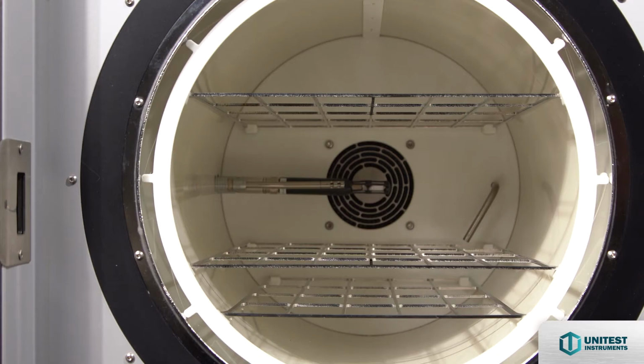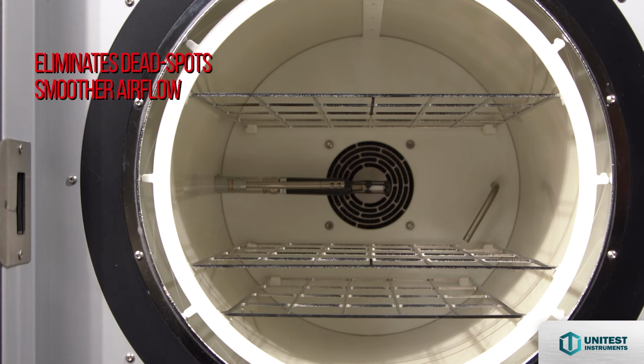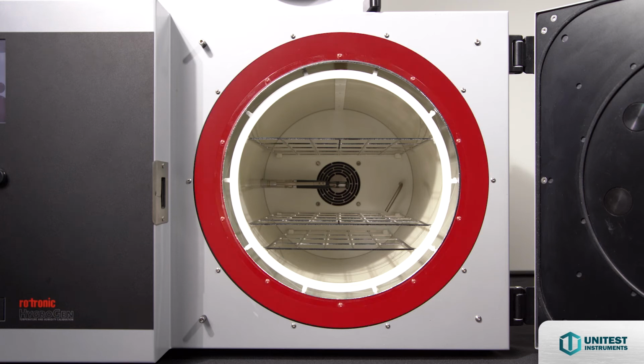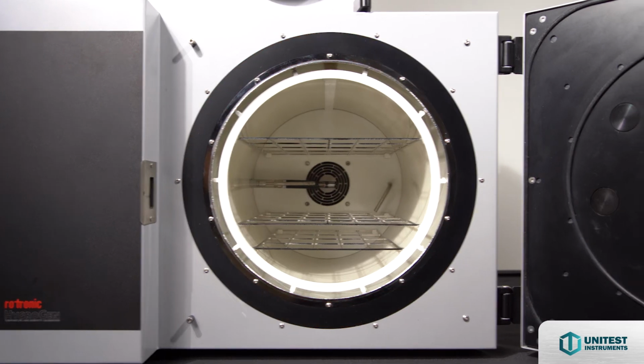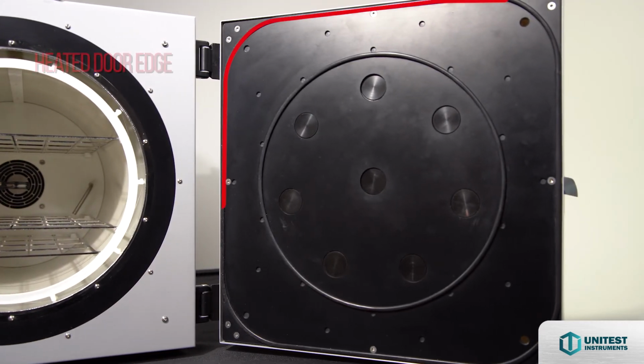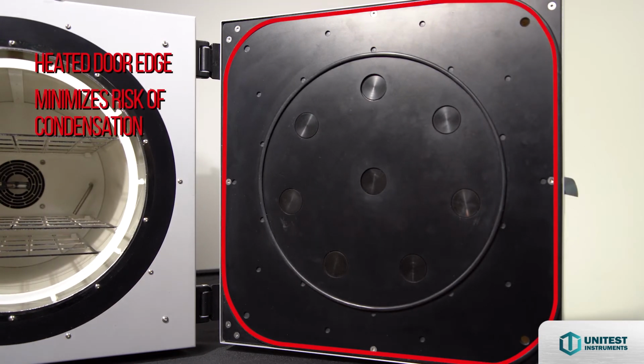The circular chamber helps eliminate dead spots which might be present in corners and allows airflows to be smoother, thereby increasing uniformity of the entire chamber. The inner sleeve design helps provide an extra layer of insulation against external influence on the generated conditions. The edge of the door is also heated to minimize risk of condensation in the chamber, which might affect measurement.